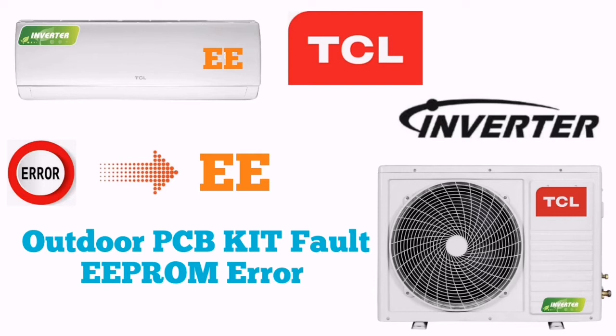And again, you have to check the EEPROM in your outdoor PCB. If it is loose or not connected properly, try to connect it properly. And again, if you are getting the same error, first change the indoor PCB and then start the unit. After changing the indoor PCB, if you start the unit and it's again showing the same problem, it means your outdoor PCB is faulty. You need to replace the outdoor PCB and your unit will be in working condition.